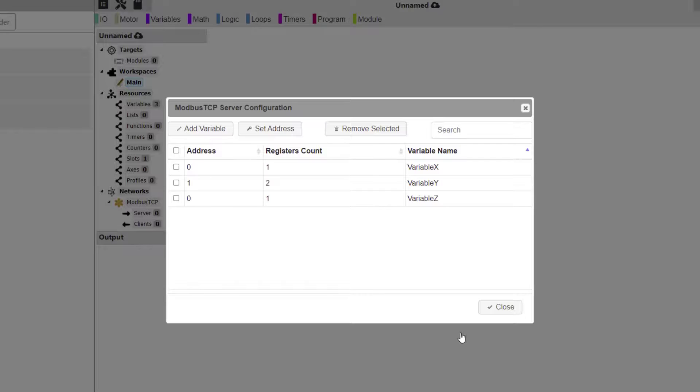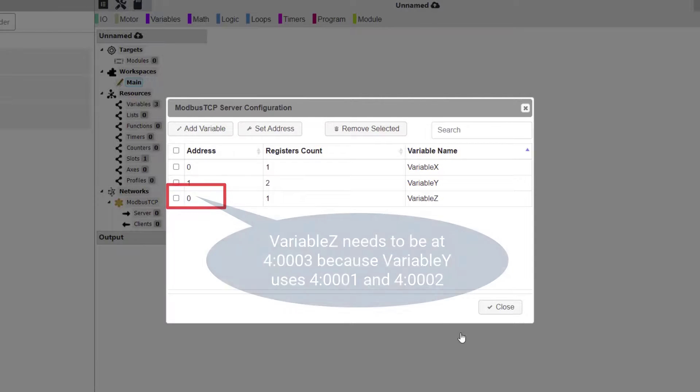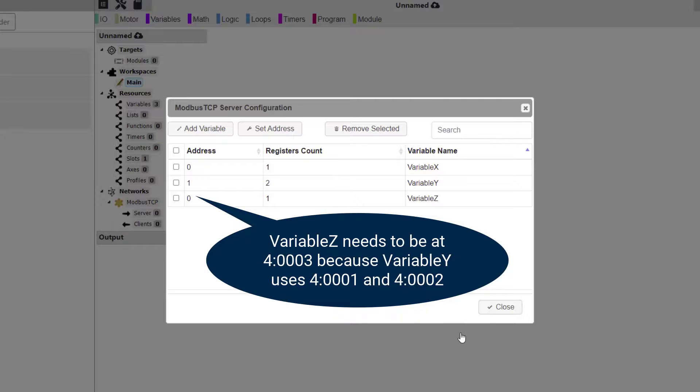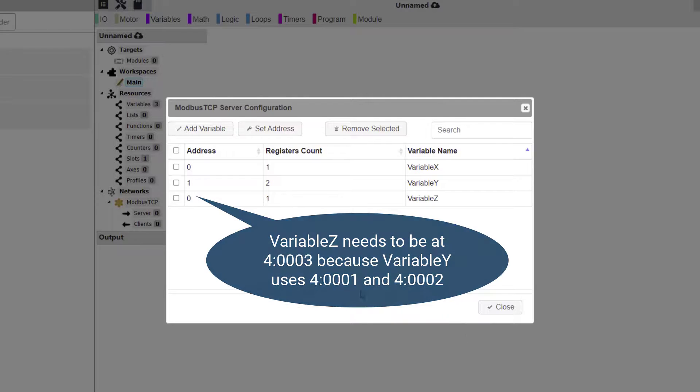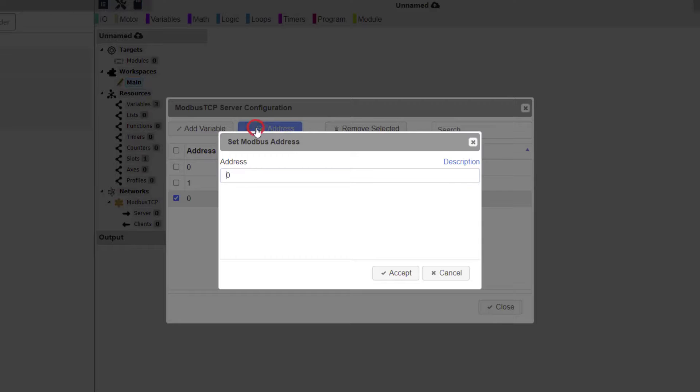Back at the Server configuration dialog window, we can see that Variable Z was added, but it defaults to Address 0. We need to change this to Holding Register Address 3. This is because our previous variable was a double integer and its data will occupy Holding Register Addresses 1 and 2. Click Set Address button and Enter a 3, and then click Accept.